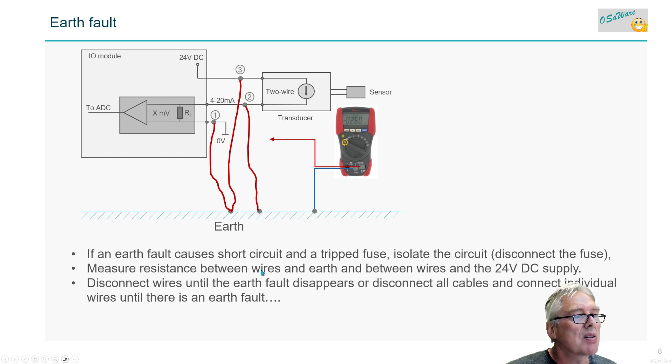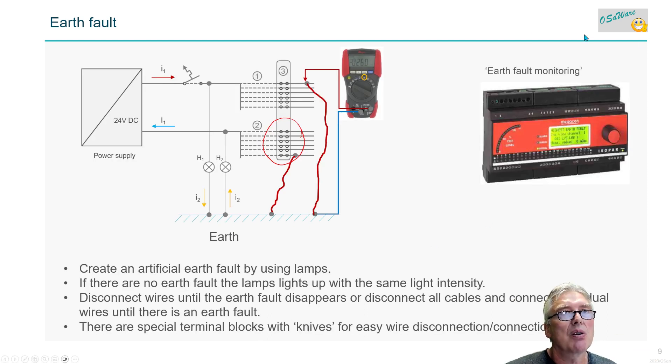Another way is to be systematic: disconnect all the cables, then connect one and one cable until you get the earth fault. The last one you connected - there's the earth fault. There is earth fault monitoring equipment, usually for high power systems. Earth fault is dangerous because you can get in contact with high voltage which is going to hurt you.